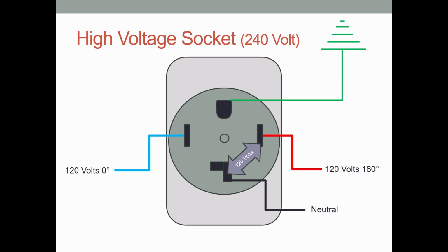Some 240 volt devices don't need a connection to the neutral wire. This is necessary if particular components inside the device require 120 volts to operate. The 240 volt wires and the plugs themselves are about 4 times heavier and not commonly used to power portable X-ray machines today.